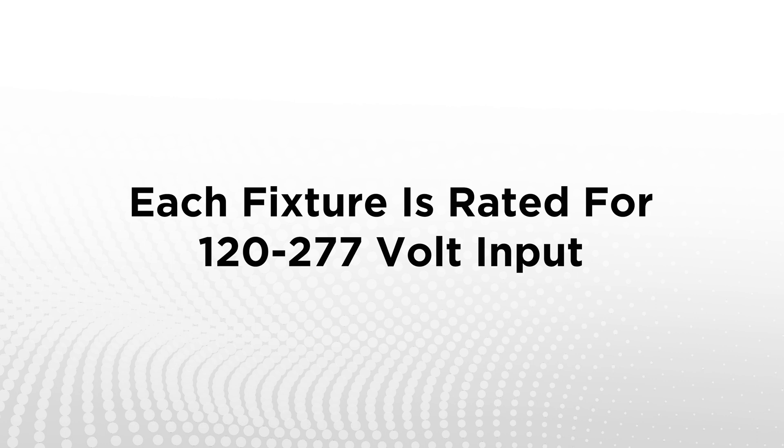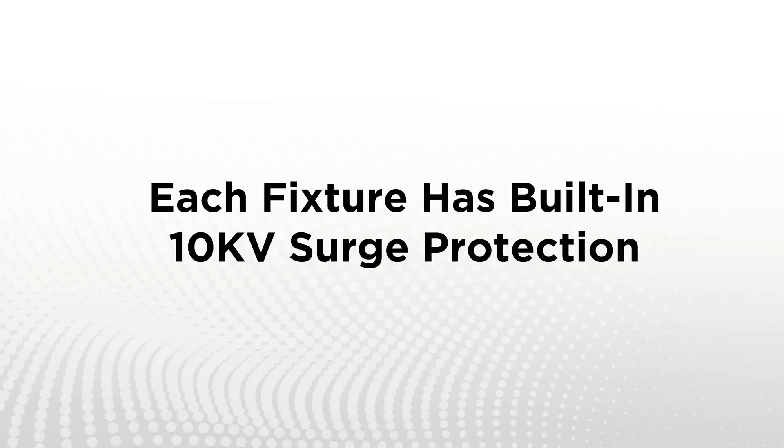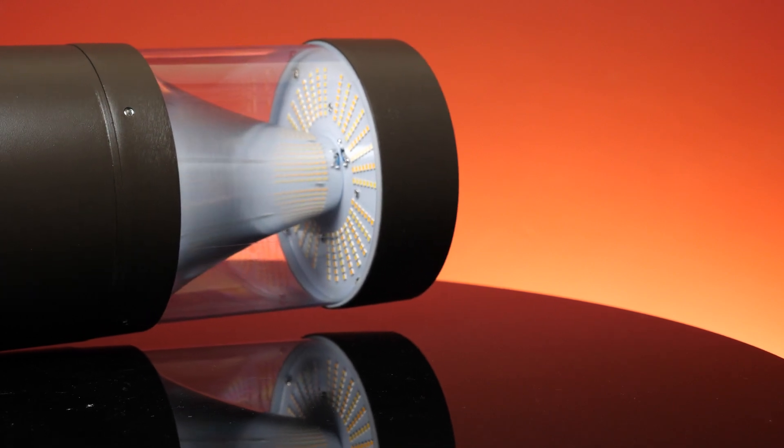Each fixture is rated for 120 to 277 volt input and can be dimmed with a 0 to 10 volt dimmer. These Bollards utilize Philips Lumula LEDs, some of the best in the industry. Each has built-in 10 kilovolt surge protection. All models have die-cast aluminum housing with a bronze powder coating to withstand demanding environments, and feature an anti-UV polycarbonate lens to resist yellowing over time.